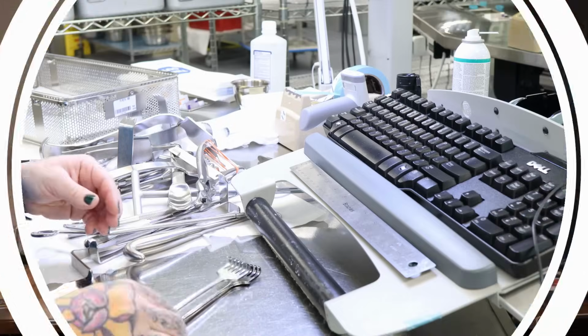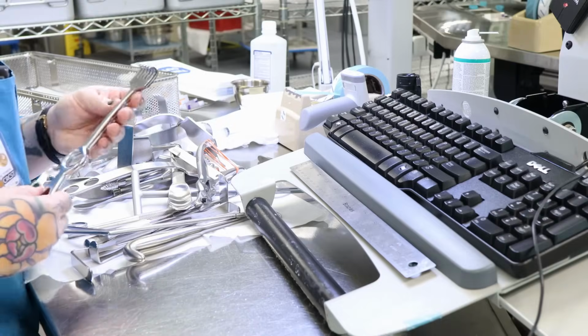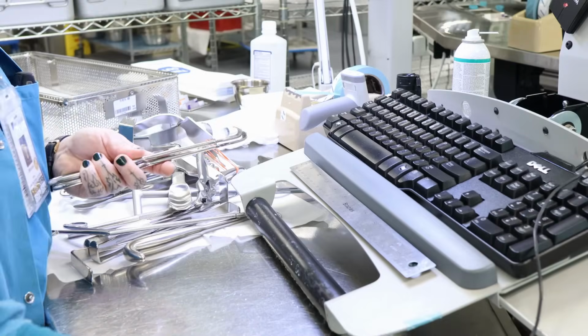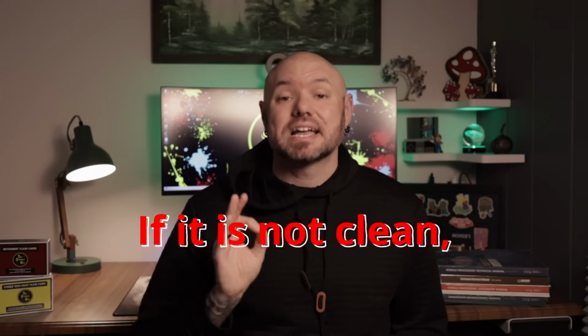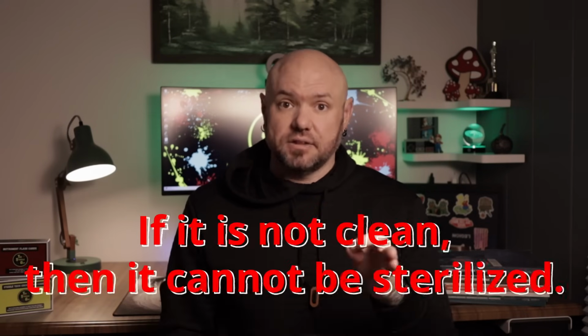Now, the first and main task with Prep and Pack is instrument inspection. The inspecting process consists of critical components. Number one, you're inspecting for cleanliness. A phrase you may often hear in the field is, if it is not clean, then it cannot be sterilized.